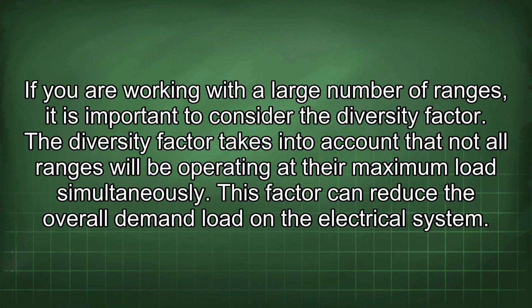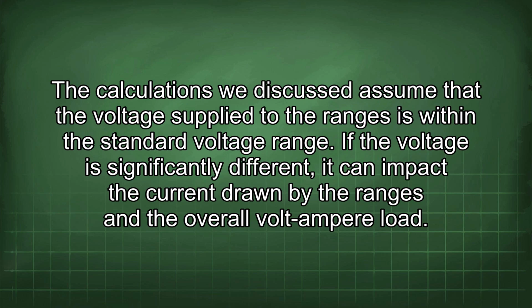If you are working with a large number of ranges, it is important to consider the diversity factor. The diversity factor takes into account that not all ranges will be operating at their maximum load simultaneously. This factor can reduce the overall demand load on the electrical system. The calculations we discussed assume that the voltage supplied to the ranges is within the standard voltage range. If the voltage is significantly different, it can impact the current drawn by the ranges and the overall volt-ampere load.